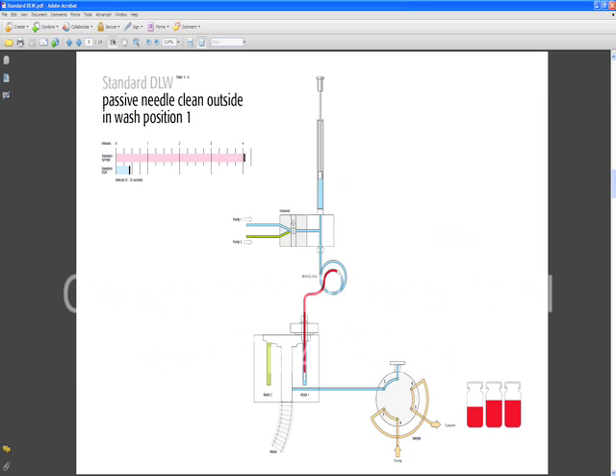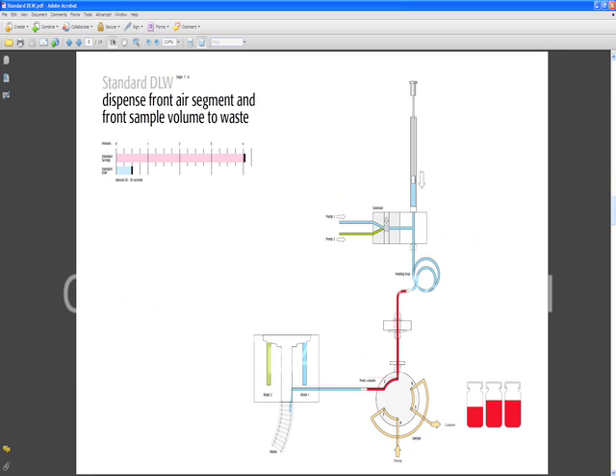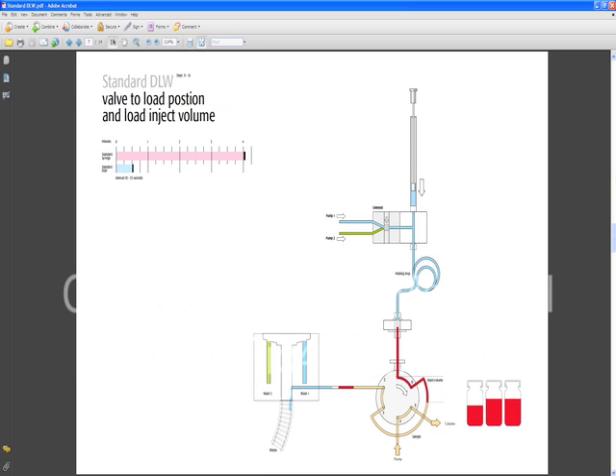We'll dip the needle which basically wets and cleans in a passive way the outside of the needle in wash one. We'll go to the valve and first push out the first portion of the sample through the inlet towards the waste. The valve switches to the load position and sample is pushed onto the loop.